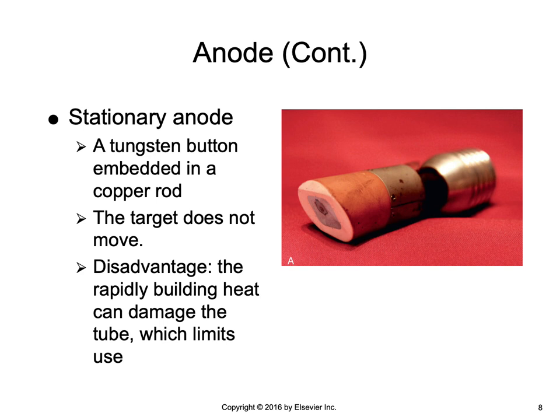There are two designs for the anode. One is the stationary anode, which is basically a tungsten button embedded in a copper rod. It is called stationary because the target does not move. Stationary anodes were used in old tube designs and may still be found in dental offices or those requiring very small exposure techniques. The primary disadvantage is that because the electrons always hit the same small target area, heat builds up rapidly and can damage the tube, limiting the exposure technique factors that can be used. This limitation spurred the development of the rotating anode design.